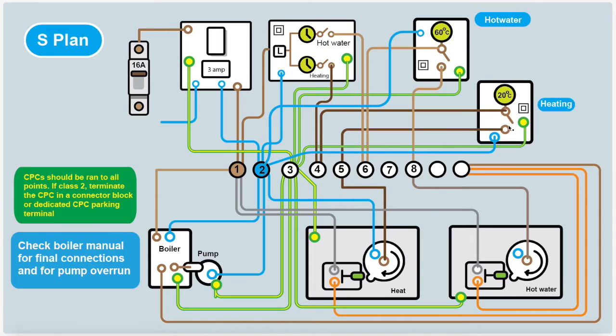So it's always a good idea to know what the actual equipment is you're going to be installing. And then you can make sure you run the right cable with the right amount of conductors in it. You don't want to be in a situation where you've run your cable and everything's been made good and plastered over and floorboards down, and you find out the specified thermostat requires a neutral, and you've only run a three-core cable. That's when people start using the CPC as live conductors. You can't use CPCs as live conductors ever.